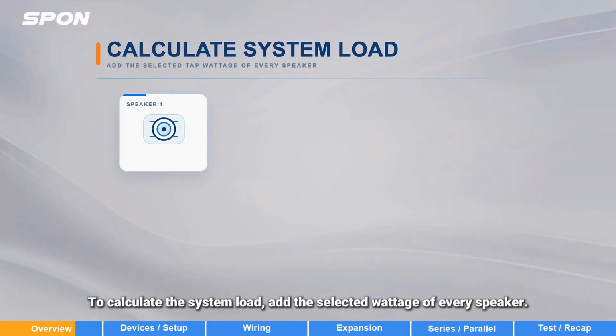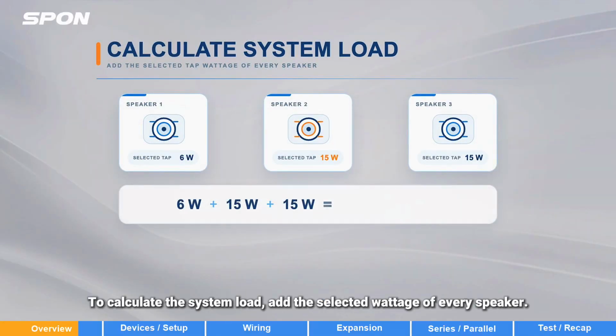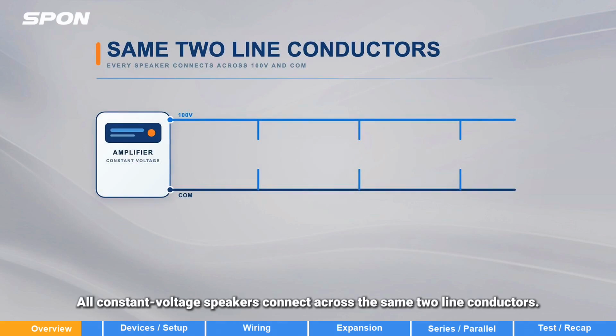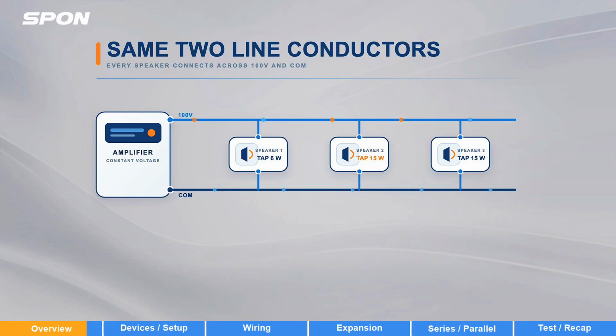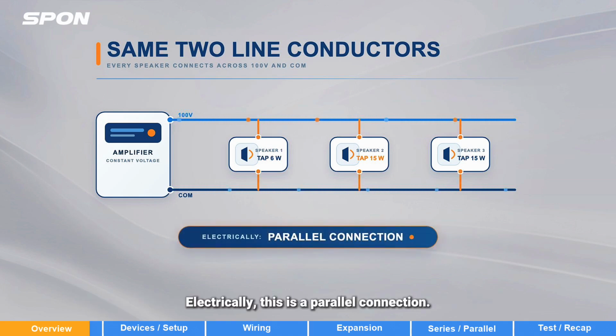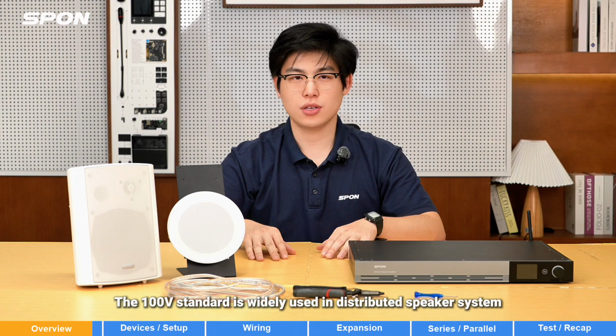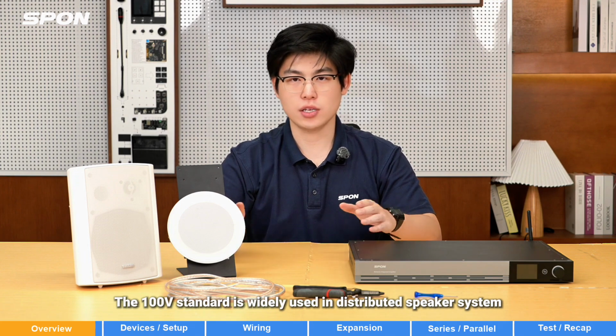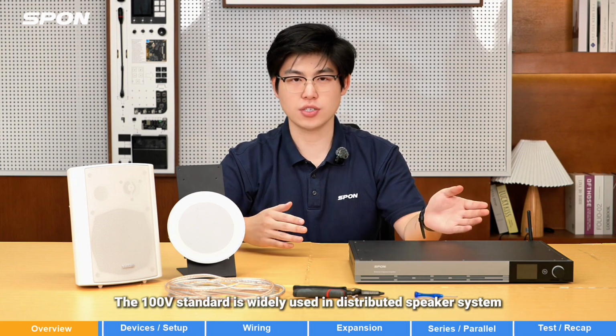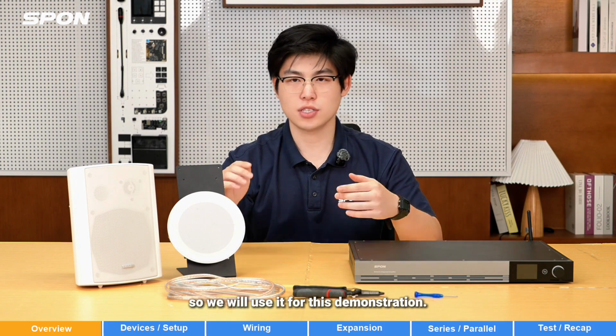To calculate the system load, add the selected wattage of every speaker. All constant voltage speakers connect across the same 2 line conductors. Electrically, this is a parallel connection. The 100 volt standard is widely used in distributed speaker systems, so we will use it for this demonstration.